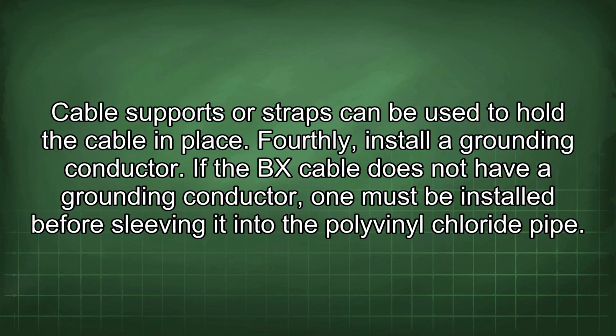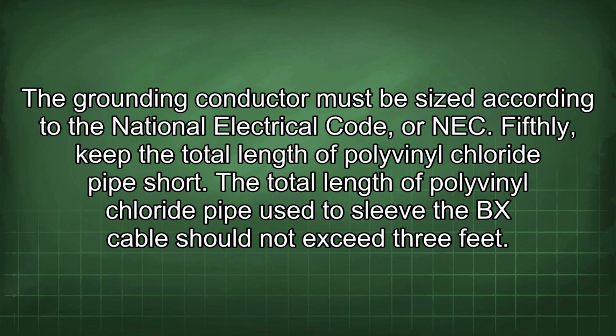Fourthly, install a grounding conductor. If the BX cable does not have a grounding conductor, one must be installed before sleeving it into the polyvinyl chloride pipe. The grounding conductor must be sized according to the National Electrical Code, or NEC.